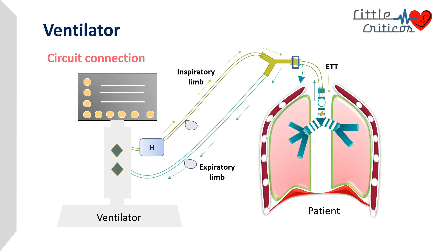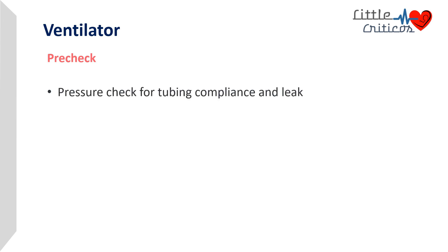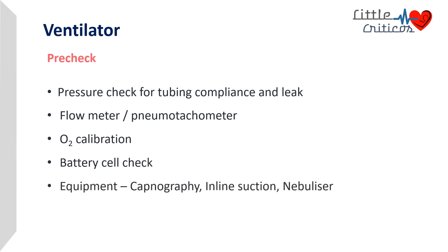In our previous lectures we discussed circuit connections, and it is very important to ensure that all components are properly set. It is important to do a pre-check before connecting the patient to a ventilator. This includes pressure check for tubing compliance and leak, checking the flow meter or pneumotachometer, calibration of the O2 cell, checking the battery source, and checking accessory equipment such as capnography, inline suction, and nebulizer.